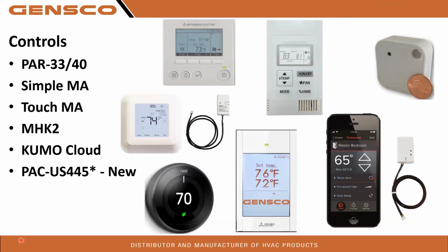Controls. So these are the different controls that we can run on these things. Again, a pretty wide variety of controls on there. You can use a PAR 33, PAR 40, simple MA, touch MA, MHK2, Kumo Cloud, or a PAC US 445 only. So if you guys still have any of the old 444s lying around, that will not work on this. You have to use the newer PAC 445 if you're going to use a 24-volt thermostat. Like I said, if you're going to use a 24-volt thermostat, PAC 445, got to have it.